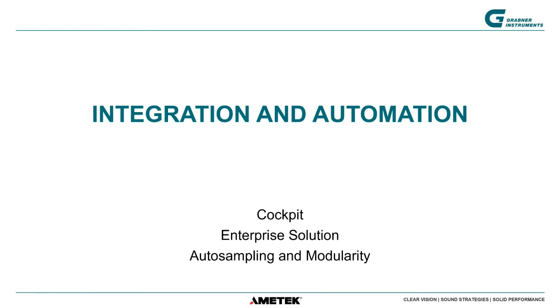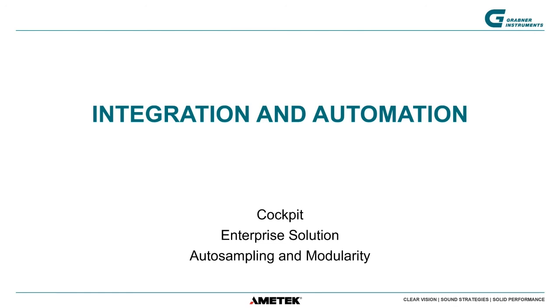Finally, integration and automation with the Cockpit software. Cockpit is the Windows software combining all the Vision instruments from Grabner Instruments. You can use it to consolidate results from multiple locations in one central lab, deploy different standard operating procedures and user roles from a single place, and ensure that every laboratory using the same instrument applies exactly the same methods, naming conventions, and user role conventions. You can also check the calibration and calibration history of every instrument, and configure and provide support to the MiniVap VP Vision and also the FP Vision. It also includes SQC and GLP compliance according to D6299.